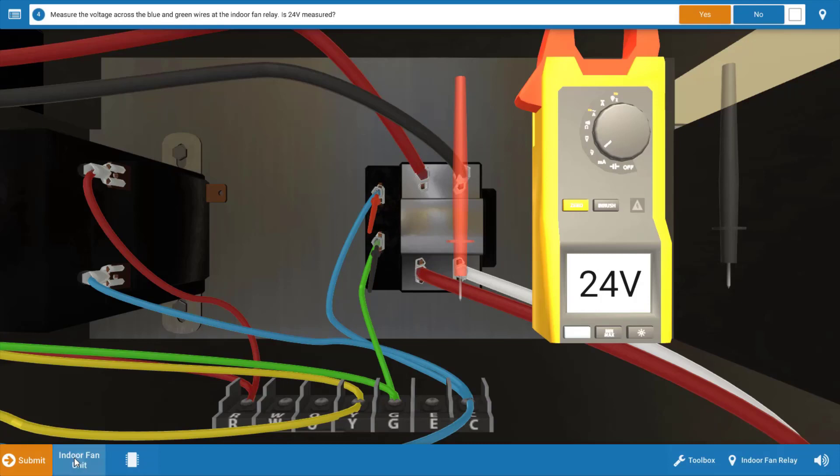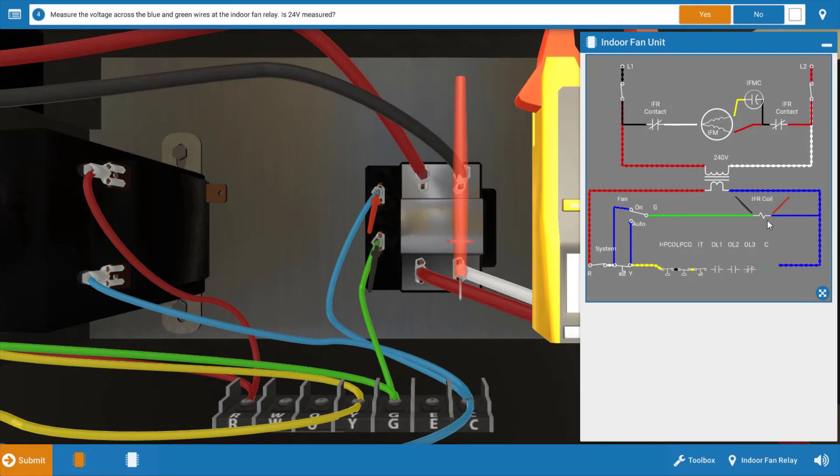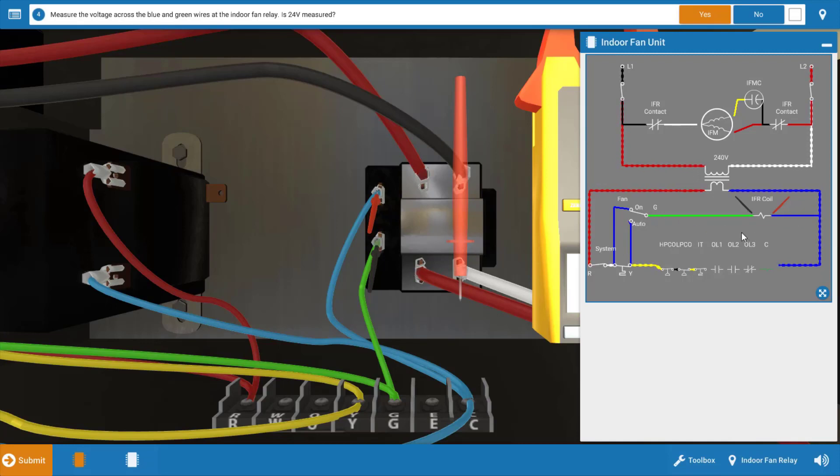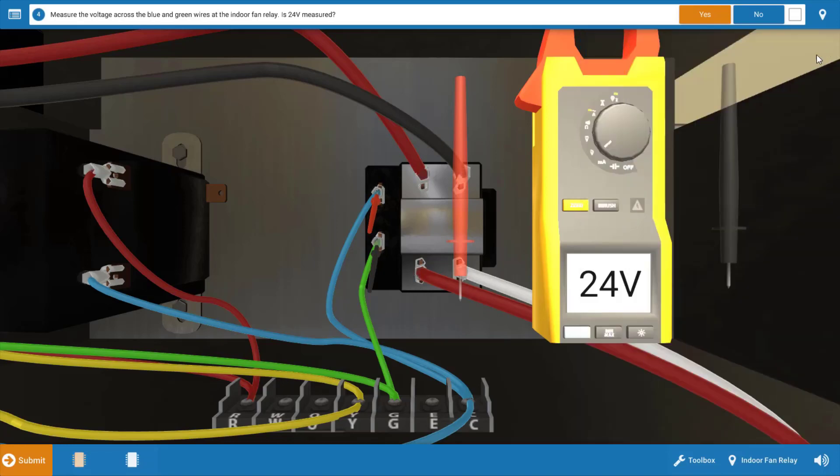Now, let's take out the wiring diagram again for just a second. We can see the placement of our meter leads at the indoor fan relay coil, and we've got 24 volts there. Well, this verifies the fan switch in the thermostat is working just fine because we do, in fact, have 24 volts at the coil. Our next step is to see if the contacts in the relay or the indoor fan relay are actually closing.